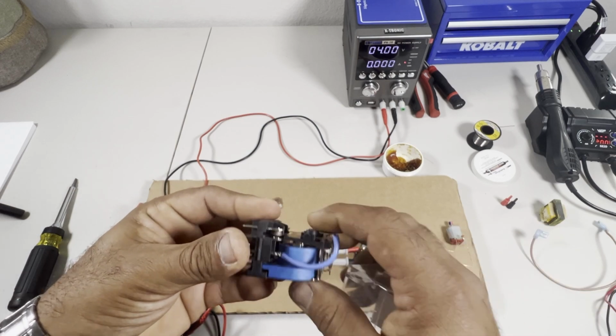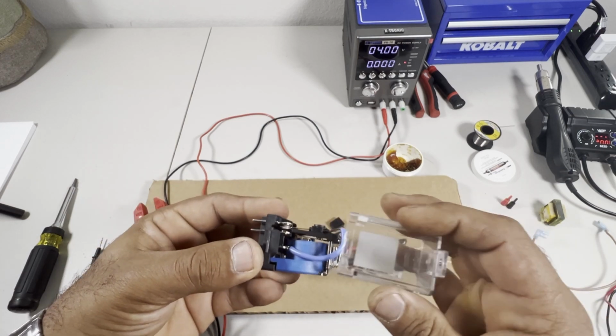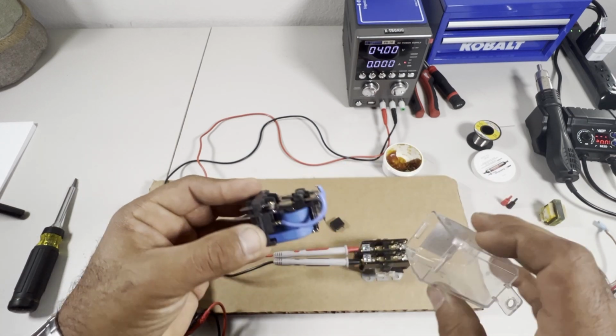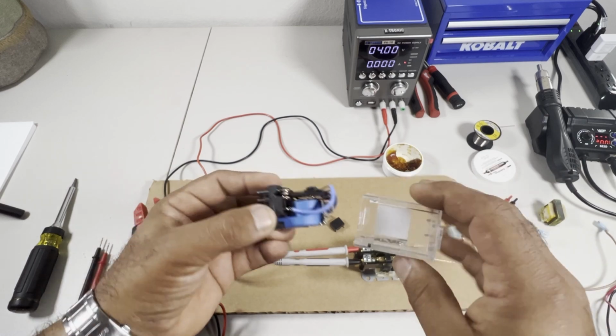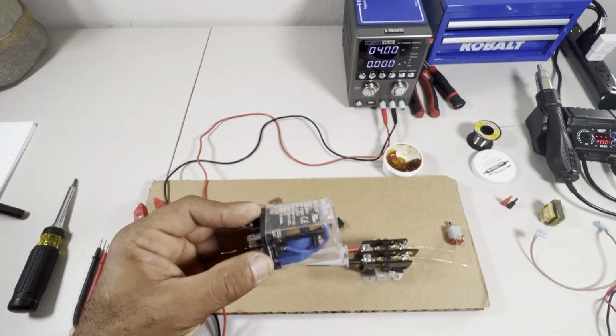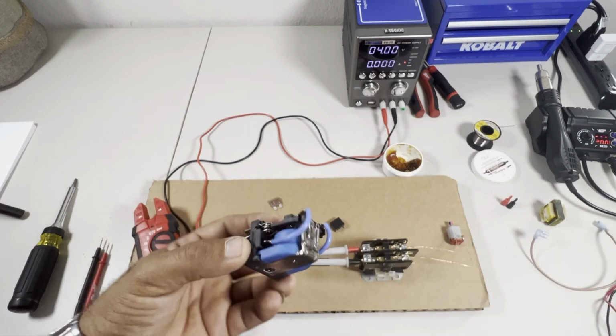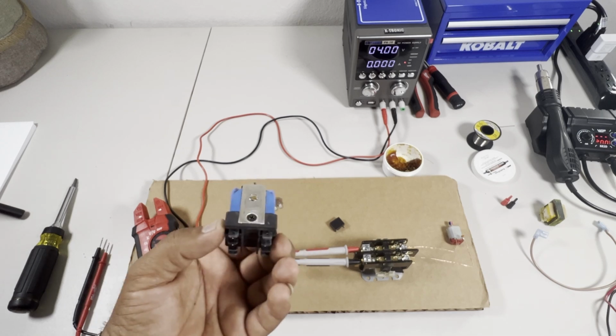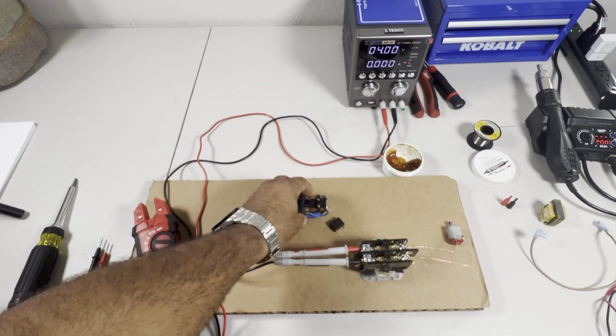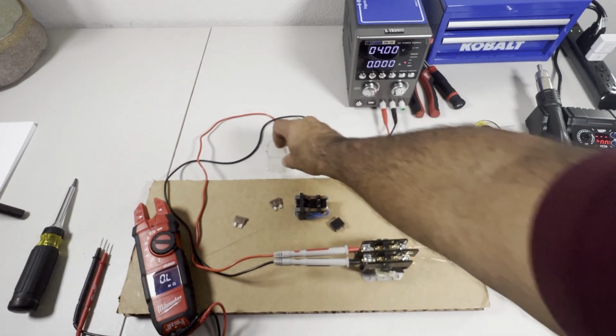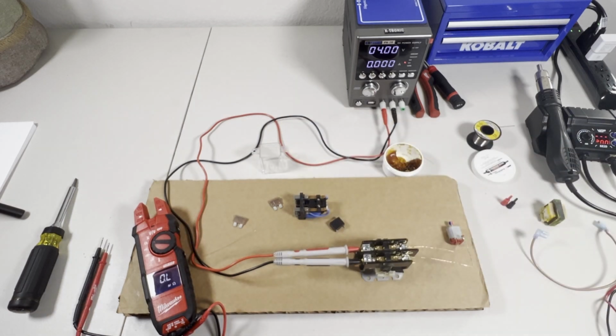It's sometimes hard to check this out with the ohm meter. A lot of the time I like to pop the cover out of them. If there's a black cover and you cannot see inside of it, I like to pop it out and take a look at the terminals myself, just to verify before I supply the high voltage power to the equipment. Relays are very simple, very easy to use.